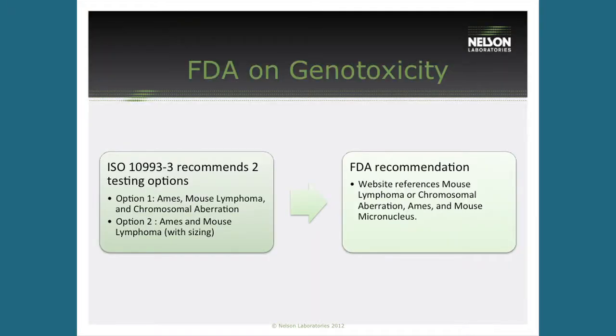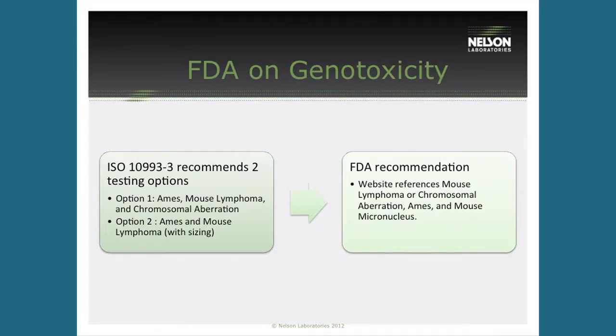Right now as ISO 10993 stands, we have two options. The first option allows us to do an Ames test, a mouse lymphoma, and then the chromosome aberration test — those three in vitro tests can be run according to ISO 10993-3 to evaluate genotoxicity. There's a second option that allows us to do the Ames and then the mouse lymphoma, and then size the mouse lymphoma colonies. By sizing those colonies we can evaluate the chromosomal damage, which allows us to replace the chromosome aberration test.